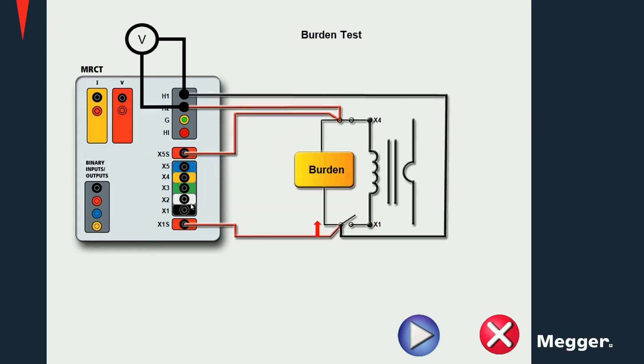To perform a burden test, remember to disconnect the current transformer from its load, since we will be testing only the impedance connected to the secondary terminals and not the secondary winding. A current will be injected in the load circuit, and the impedance will be then calculated.